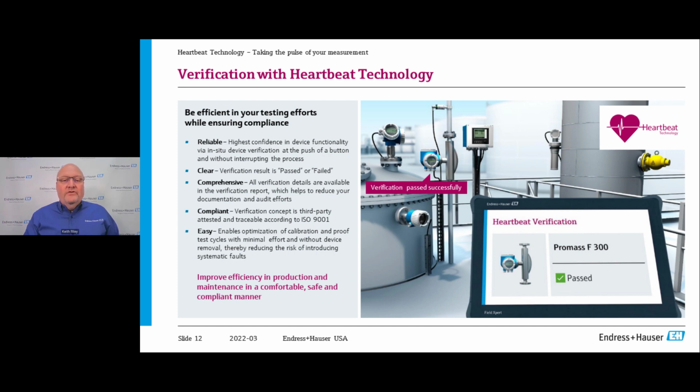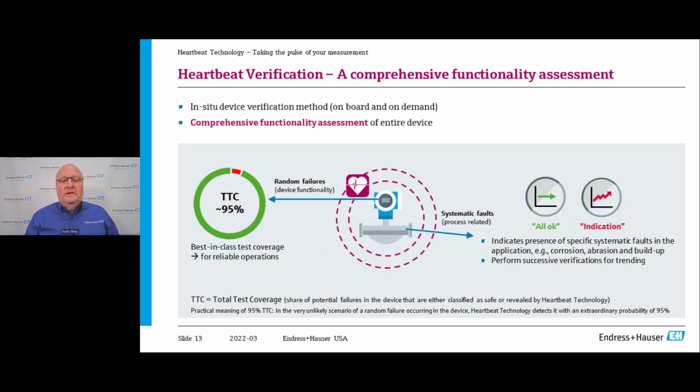The next thing we're going to transition to is verification. This is our predictive portion of heartbeat. All right, heartbeat verification is first and foremost a qualitative assessment of the device. And there is a distinction. I'm using verification. It is not considered a calibration, which would be a quantitative evaluation. It is verification, which is a qualitative.